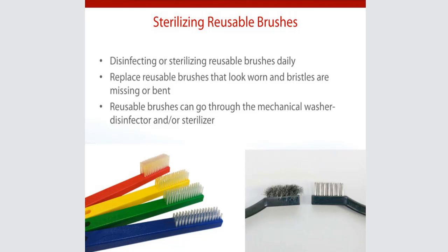But when you start seeing a brush that looks like you stood on it, it's time to replace that brush. If you do have any brushes for instruments, they should be the long-handled brushes like you see on the left. They should not look like a nail or a hand brush that you would commonly use, because you're going to have a higher chance of an accidental percutaneous injury. Make sure that you do disinfect or sterilize reusable brushes. Read the IFUs before you put a brush with a plastic body in your sterilizer. You don't know that they all are compatible with steam sterilization.